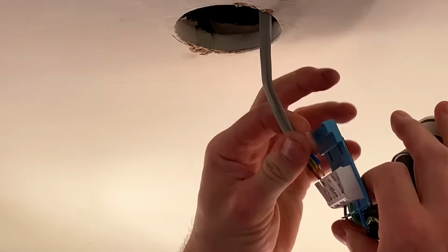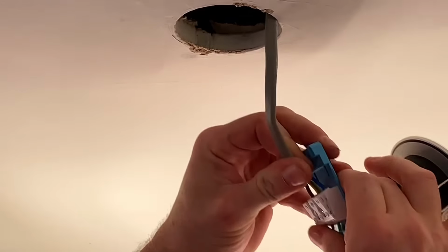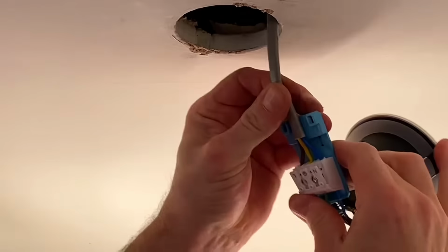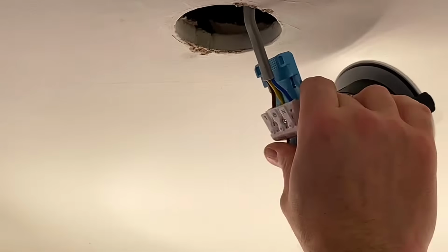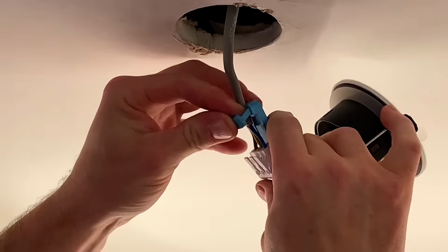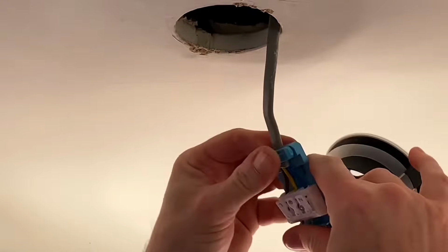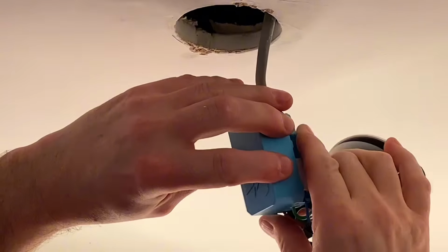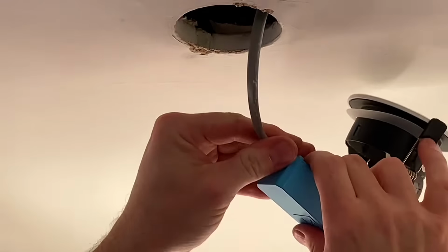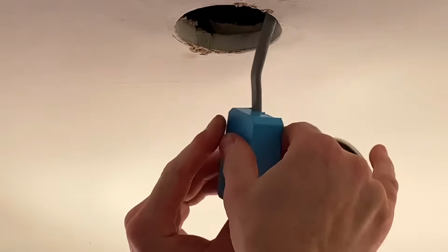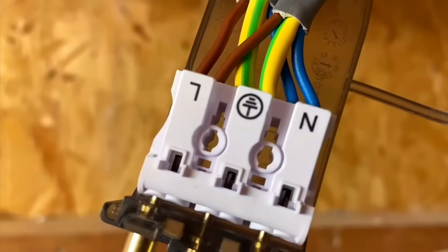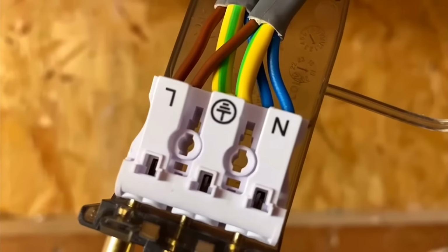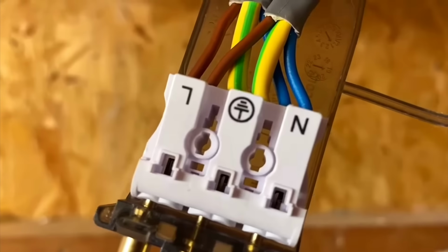And we can see how this 2-plate method reduces the number of cables here at the lighting point. Very important when we're fitting downlighters, LED spotlights, etc., that we reduce the number of cables, and by using the 2-plate method, it means we've cut down the number of conductors. If we want another light to come on at the same time, the neutral, the switching line and CPC would loop round to the next light, to the next light, to the next light, meaning that we get a maximum of 2 cables per downlighter.